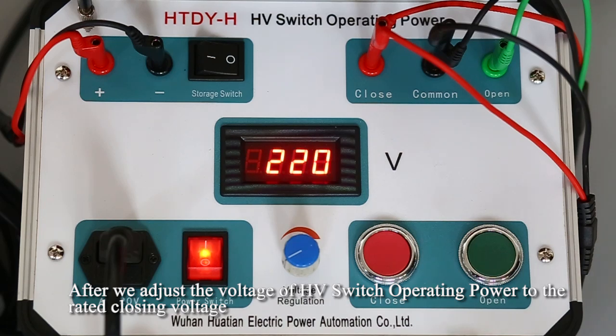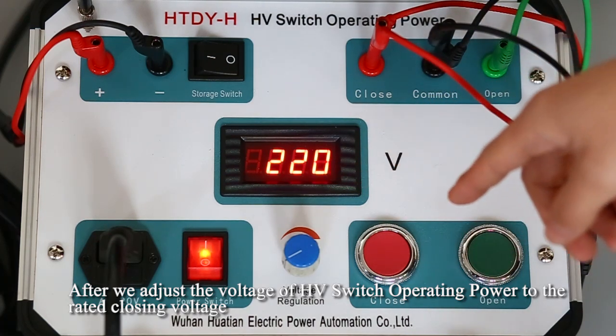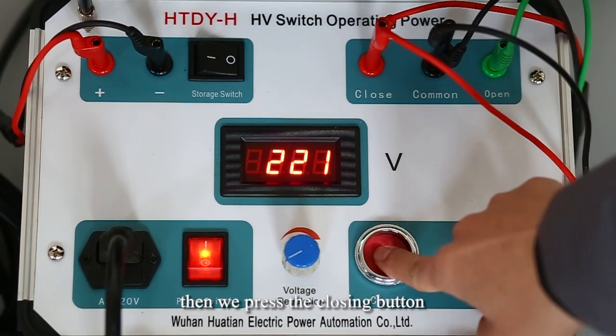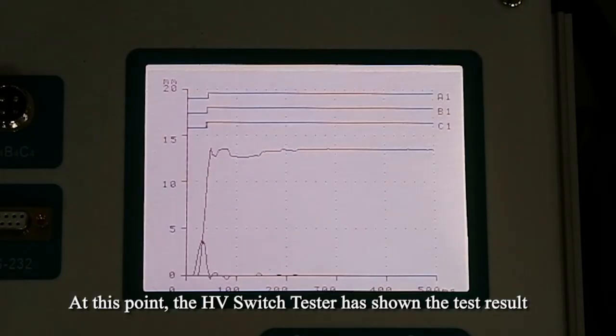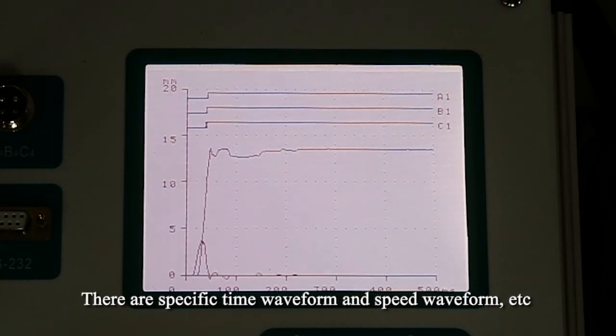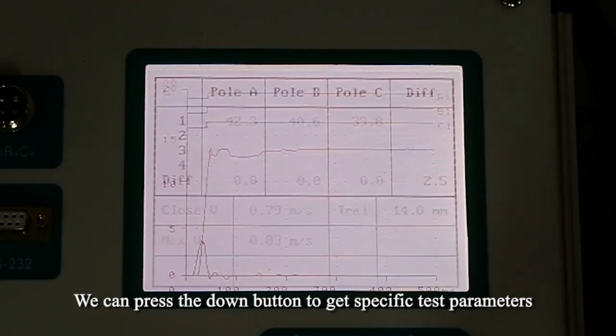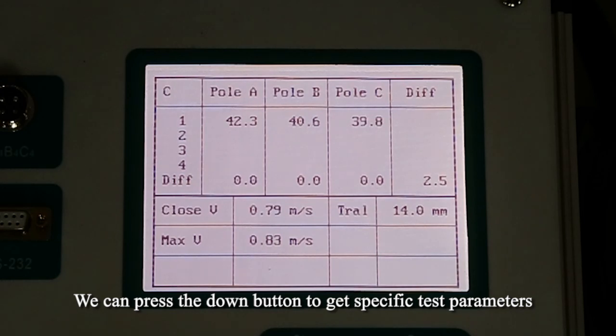After we adjust the voltage of the high voltage switch operating power to the rated closing voltage, we press the closing button. At this point, the high voltage switch tester shows the test results. There are the specific time waveform and the speed waveform, etc. We can press the down button to get specific test parameters.